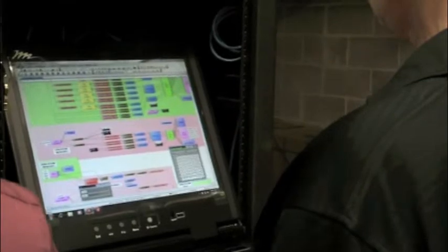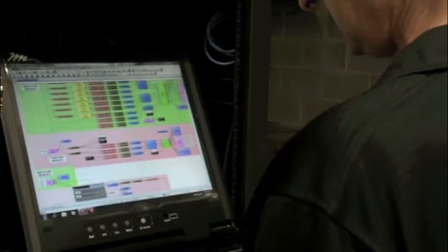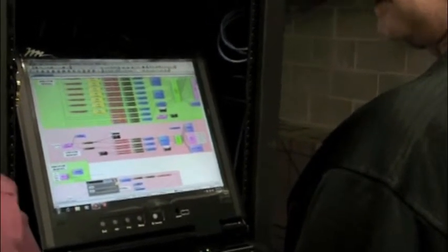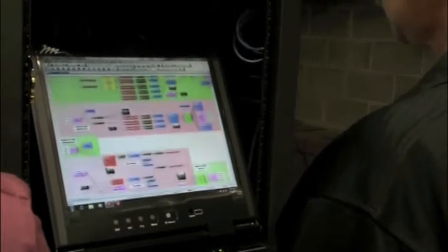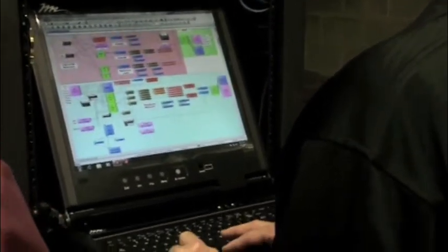I'll show you where that control is, so you can make sure that it actually is activated properly by the electricians. We told the electricians that it's set for normally open. When the system is not in an emergency condition, their relay is set to open. In an emergency condition, their relay is set to close. And when this sees a closure, the logic control will activate that preset. So really that's pretty much it in a nutshell.